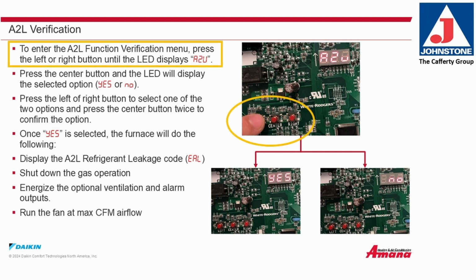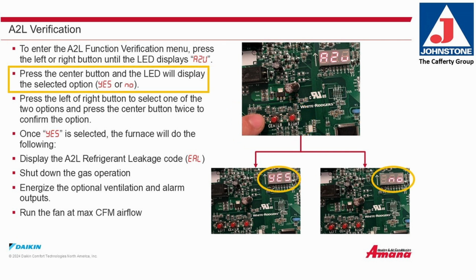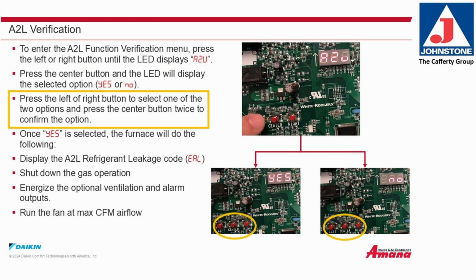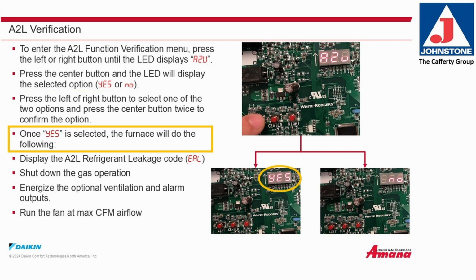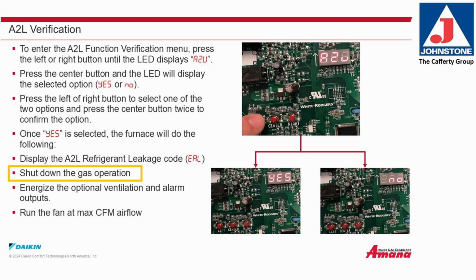To enter the A2L verification menu, press the left or right button until the LED displays A2U. Press the center button and the LED will display the select option yes or no. Press the left or right button to select one of the two options, and press the center button twice to confirm that option. Once yes is selected, the furnace will do the following: display A2L refrigerant leakage code, EAL, shut down the gas operation, energize the optional ventilation and alarm outputs, run the fan at maximum CFM airflow.